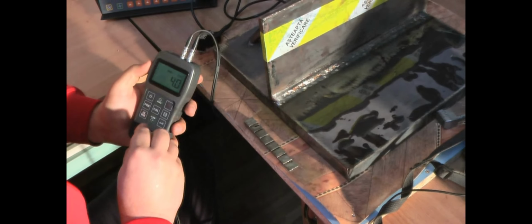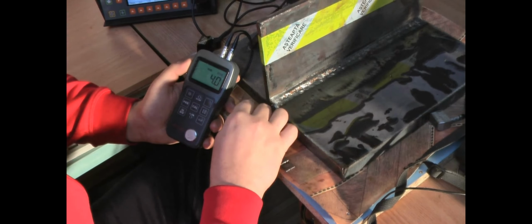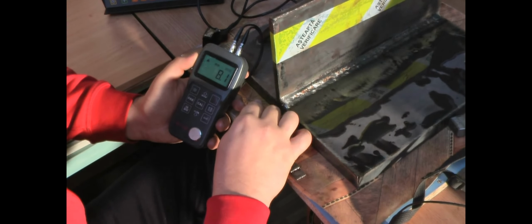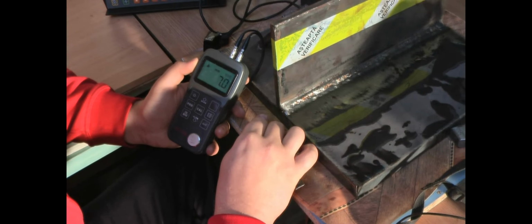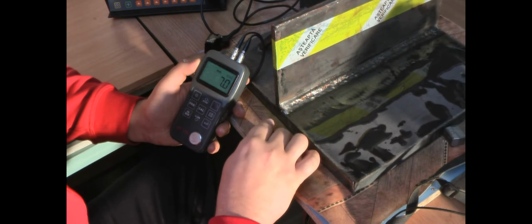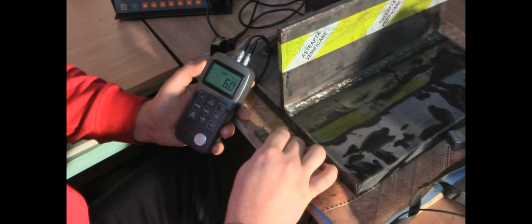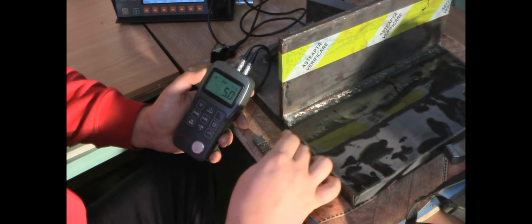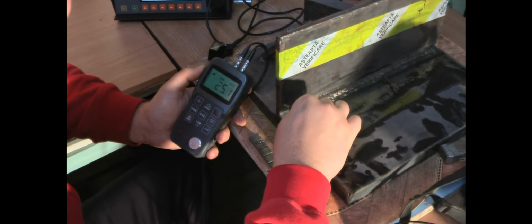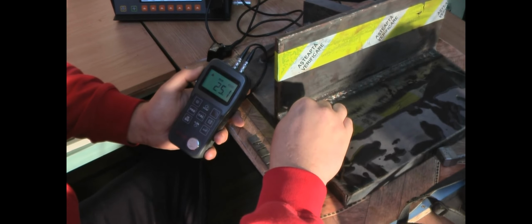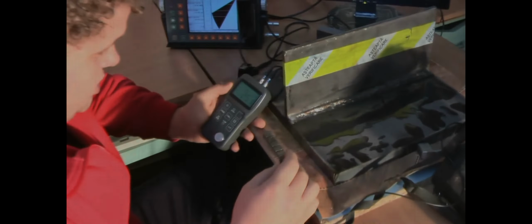Ultrasound testing. Thickness. This method is used to determine the wall thickness in pipes, boilers, high-pressure vessels and other items according to customer requirements. You can watch now the calibration of the device before starting the examination. Calibration is performed using a 3-step calibration block, to verify the accuracy of the information obtained. The original thickness of the examined elements is 6 mm, so the sizing is made at 4 mm, 5 mm and 6 mm.